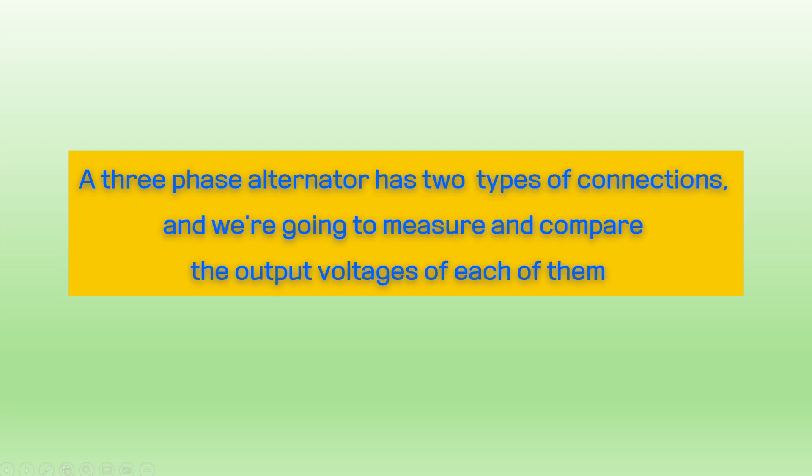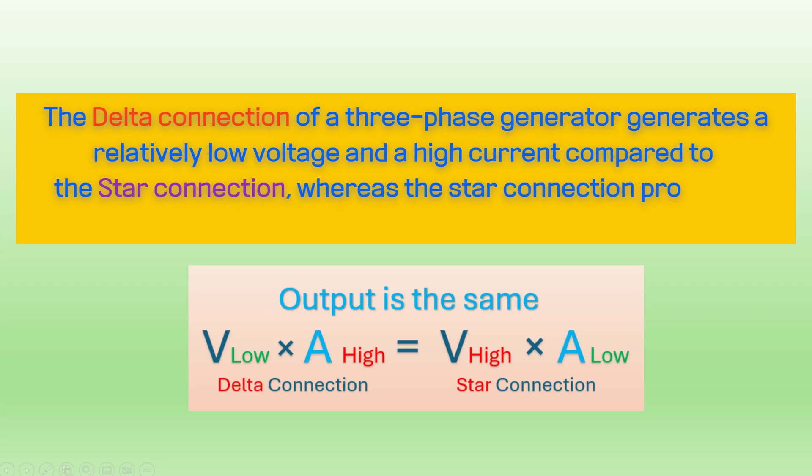A 3-phase alternator has two types of connections, and we're going to measure and compare the output voltages of each of them. The delta connection of a 3-phase generator generates a relatively low voltage and a high current compared to the star connection, whereas the star connection produces a high voltage and a low current.